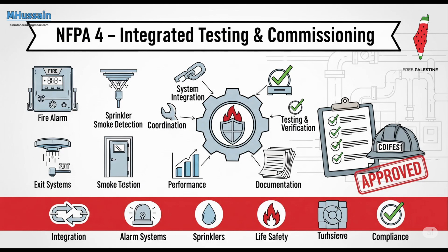Safety first, always. So during the actual integrated testing, what functions need to be checked? Is it just the fire alarm and sprinklers? Oh no, it's comprehensive. All required building functions that are part of the integrated system must be verified. That includes sprinkler system alarms, but also egress lighting activation, smoke control systems, elevator control and recall, fire alarm signaling, both internal and maybe to the fire department, fire pump operation, potentially security system interactions like door unlocking, HVAC controls shutting down or going into smoke mode, and any special suppression systems. Wow. It's really touching almost every major building system that plays a role in an emergency. If it's integrated for life safety, it needs to be part of the integrated test.